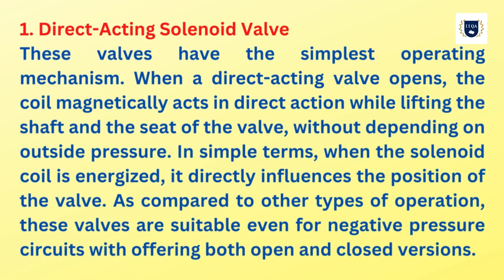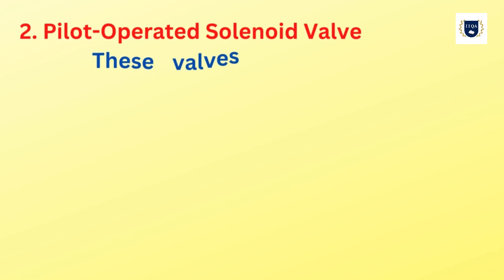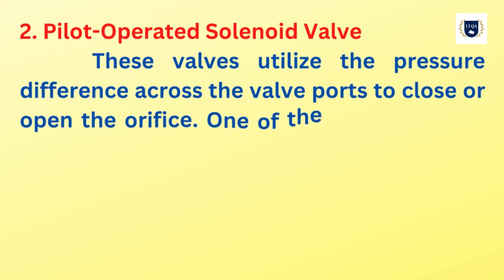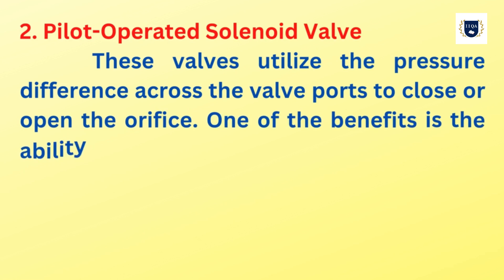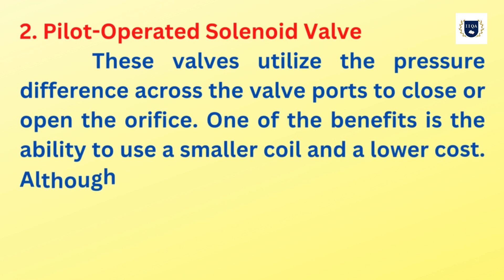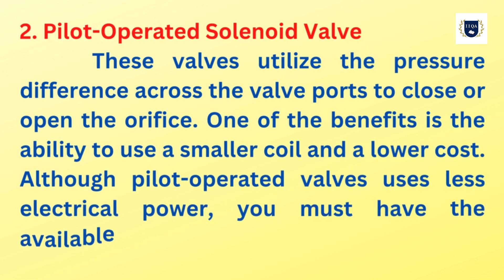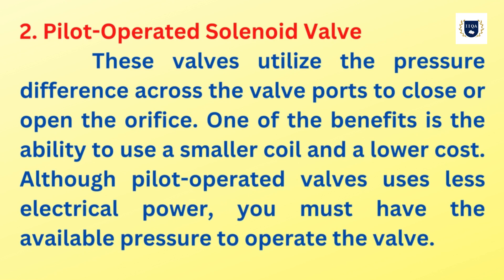Two, pilot operated solenoid valve. These valves utilize the pressure difference across the valve ports to close or open the orifice. One of the benefits is the ability to use a smaller coil at a lower cost. Although pilot operated valves use less electrical power, you must have the available pressure to operate the valve.